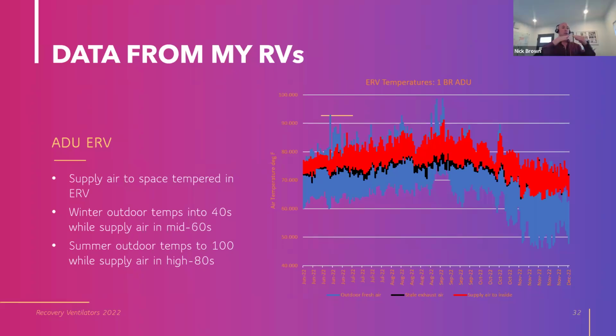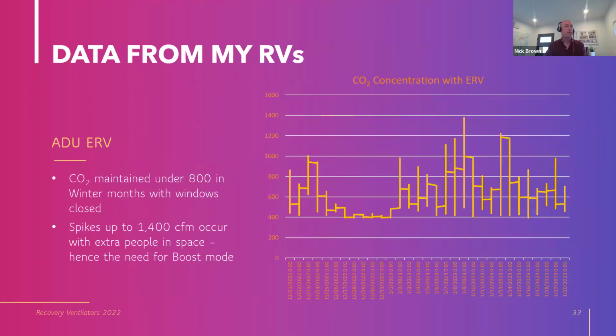But also notice the supply air isn't right in the middle of the outdoor air range. It's bumped up a little, and that's the impact of the fan heat. Okay? Makes sense? So in the summer, the outdoor temperature goes up to the hundreds, and the supply air is in the high 80s. In the winter, outdoor temperatures are down in the high 40s, and supply air is in the mid 60s. Makes sense?